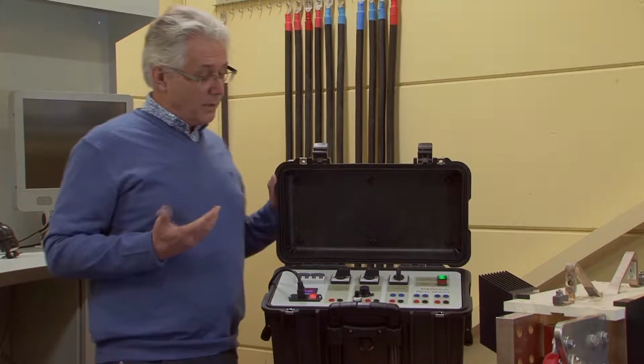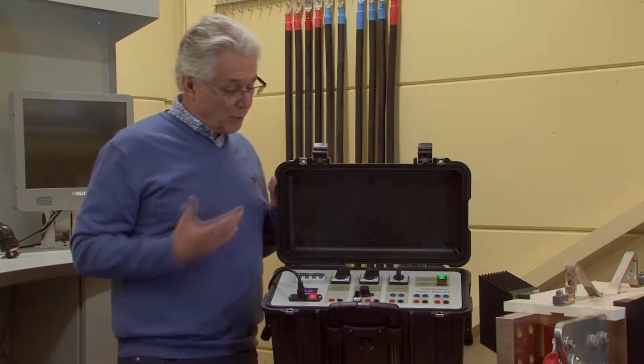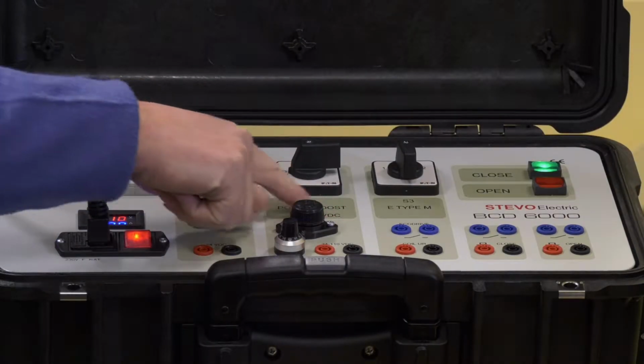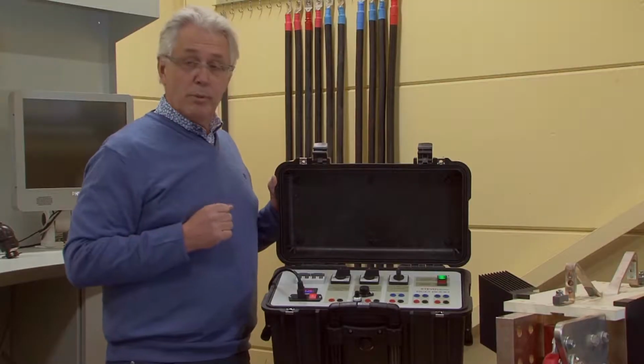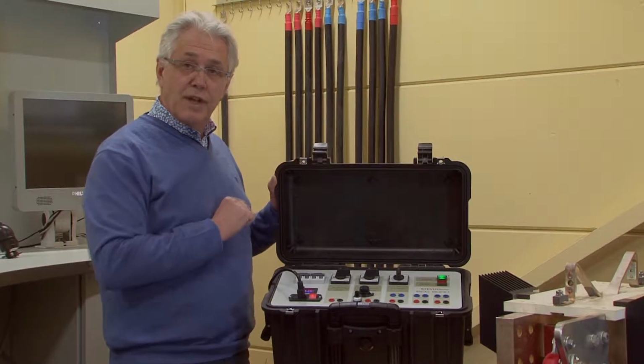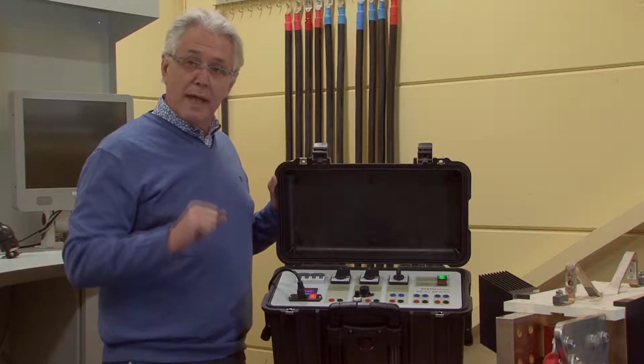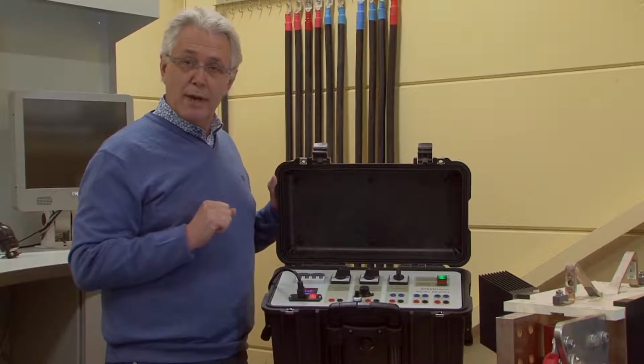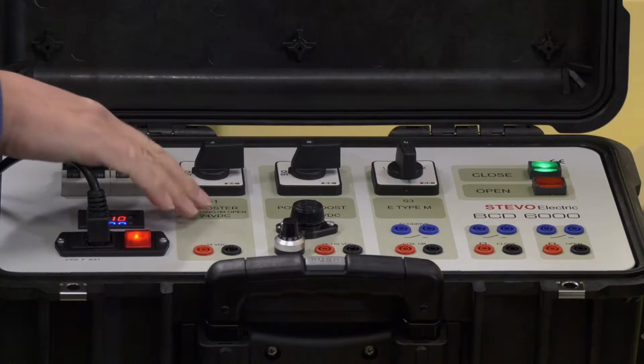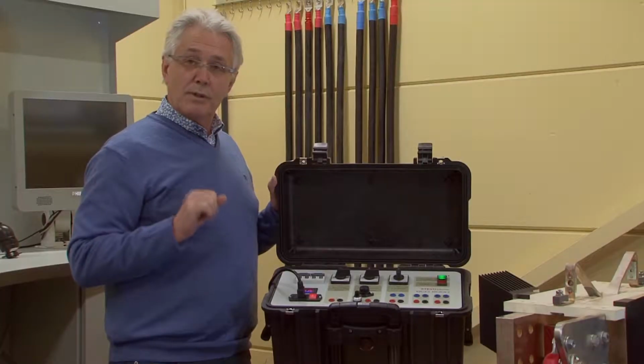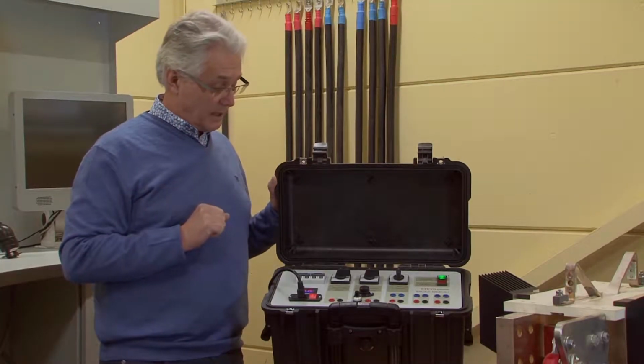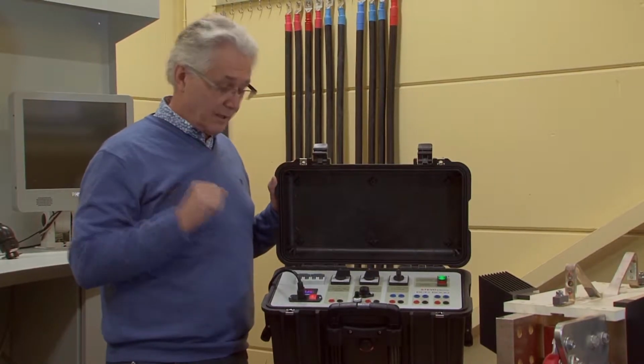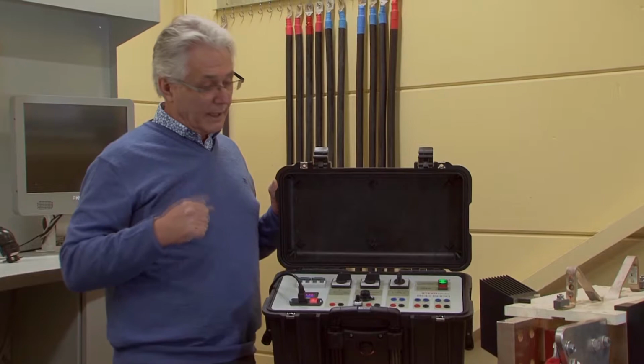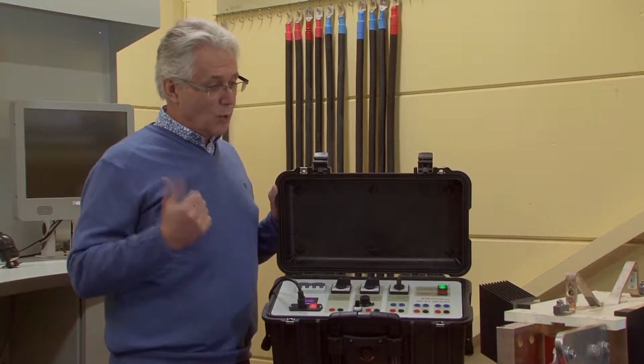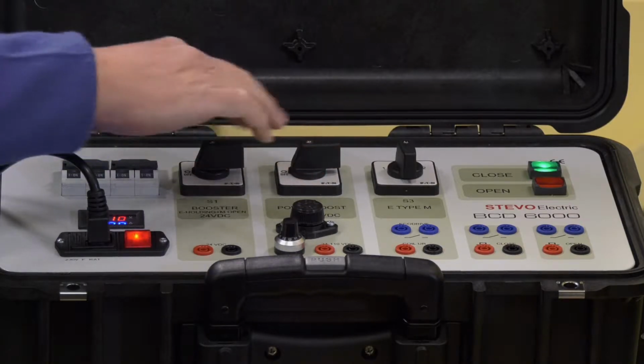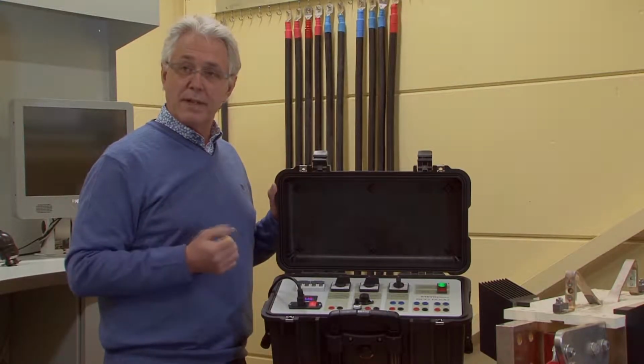Depending on the power you need, we have built in some extra booster functions. This is the power boost module, and with the power boost module this allows you to generate a very powerful impulse to push the breaker in a closed position. This booster function, it's on the 24 volts, allows us to increase the electric holding current, or for a magnetic holding, increase the current to open the breaker. So these two buttons are used to increase the power for heavy breakers.